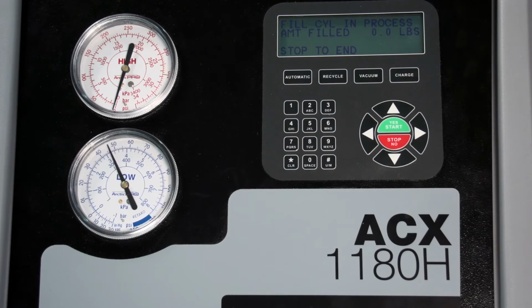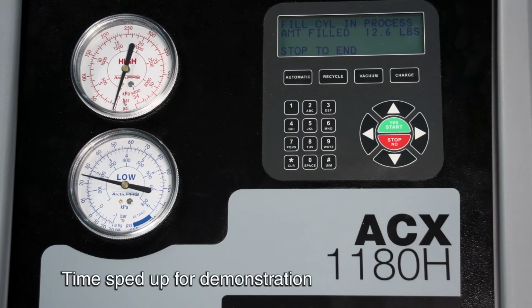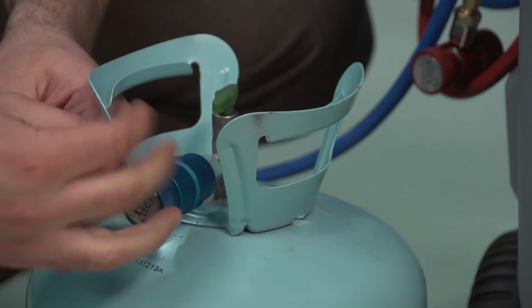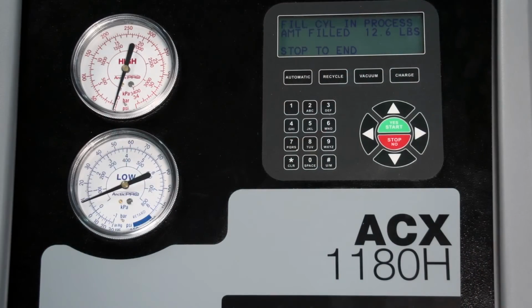The machine will then start the fill process. It can take up to 2 minutes for the weight to increase. The first time you fill the internal cylinder can take a while because the tank is completely empty. The ACX1180 is preset from the factory to fill to 17.6 pounds. When the cylinder is full, close the valve and the hose. The machine will then circulate the refrigerant for 5 minutes.